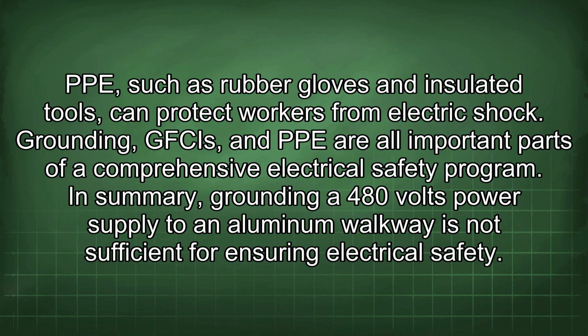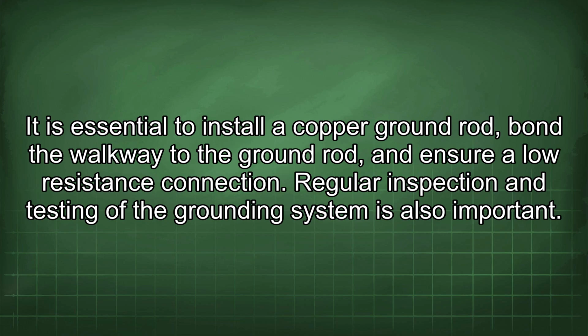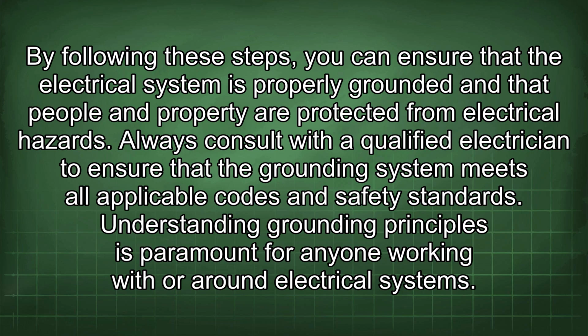In summary, grounding a 480 volts power supply to an aluminum walkway is not sufficient for ensuring electrical safety. It is essential to install a copper ground rod, bond the walkway to the ground rod, and ensure a low resistance connection. Regular inspection and testing of the grounding system is also important. By following these steps, you can ensure that the electrical system is properly grounded and that people and property are protected from electrical hazards. Always consult with a qualified electrician to ensure that the grounding system meets all applicable codes and safety standards.